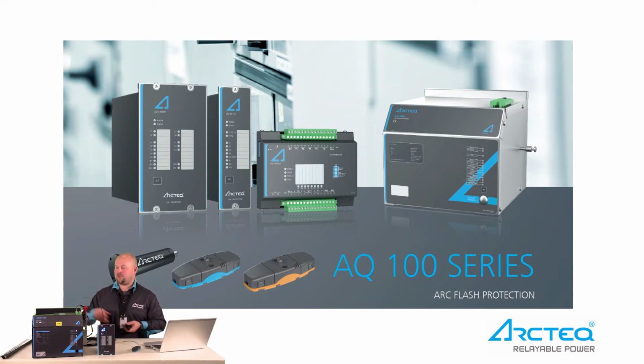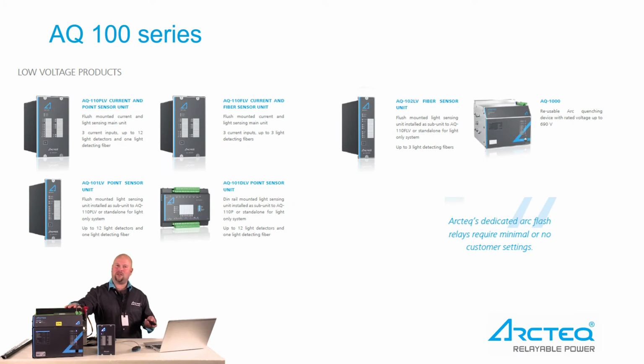Today's topic was this AQ1000 arc quenching device, testing and commissioning. And reminder that AQ1000 belongs to the well-known, well-proven AQ100 Arc Flash Protection series, Arc Flash Protection System, and it is part of it. Low voltage 690 volts, tested 200 kiloamps, operation time 2 milliseconds, mechanical operation time, closing time 2 milliseconds. Part of the AQ100 low voltage series.